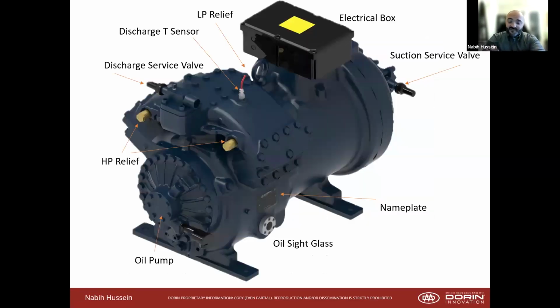Here is our compressor as an example. You have the suction service valve right here. You have the electrical box, the nameplate, very important to know where that is, and always look at nameplates whenever you look at a compressor. Oil sight glass, you check that to make sure that you have 1/4 level oil. Some other compressors may suggest 2/3. Ours is 1/4 of that sight glass.